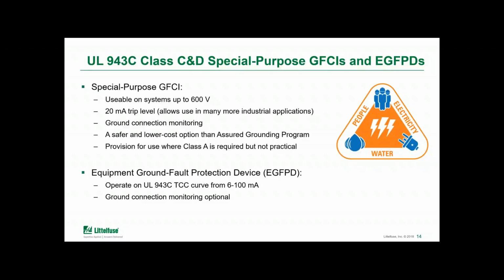Now you might say, hold on a second, I thought 6 milliamps was required as a pickup for personnel protection, and how does 20 milliamps really qualify? The answer is that although these new classes of GFCIs do trip at 20 milliamps, they actually follow the same inverse time curve that is defined by UL 943, meaning that the trip time of a Class C or Class D at 20 milliamps is actually faster than a Class A at 6 milliamps. So that gives protection based on that same inverse time curve.